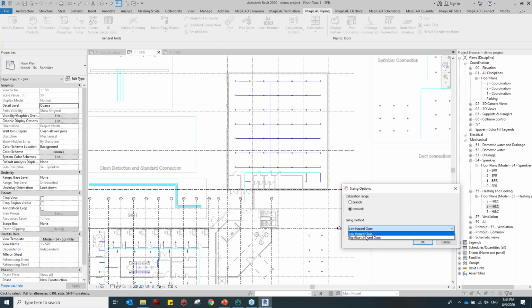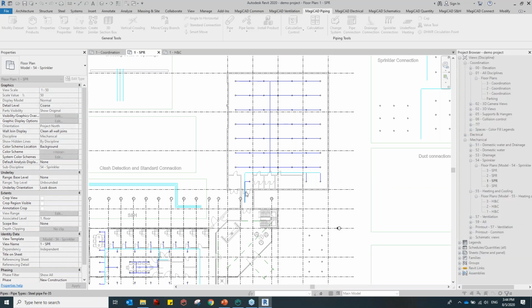Here I have the two tables. I've selected the low hazard class, which is a general table applicable for all the areas. I click OK, and then select the network. If I select any piece of the network, it will automatically identify the feed point and start doing the sizing from that point.